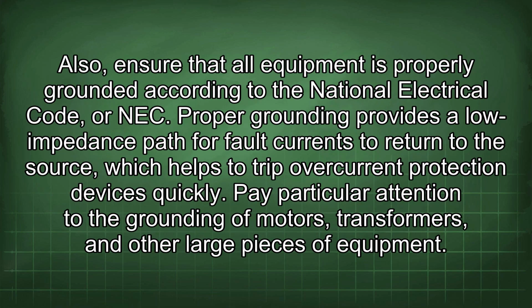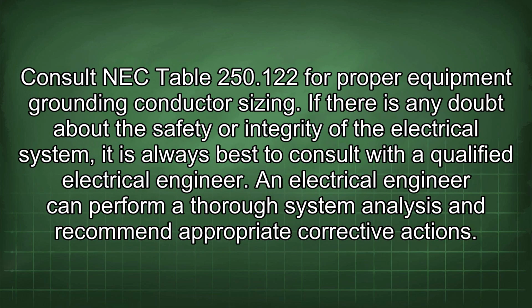Also, ensure that all equipment is properly grounded according to the National Electrical Code, or NEC. Proper grounding provides a low impedance path for fault currents to return to the source, which helps to trip overcurrent protection devices quickly. Pay particular attention to the grounding of motors, transformers, and other large pieces of equipment. Consult NEC Table 250.122 for proper equipment grounding conductor sizing.